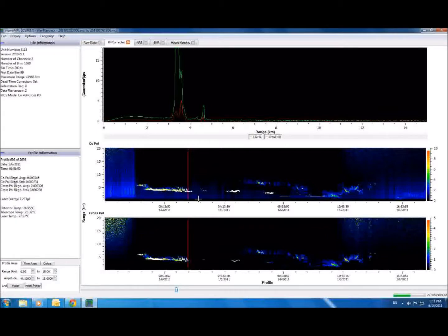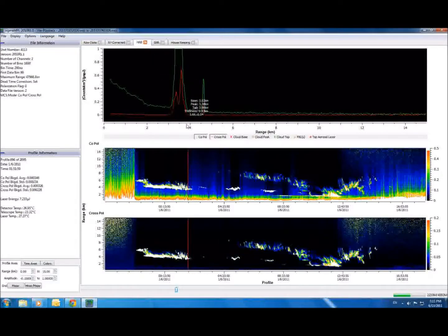The next step in post-processing is what we call the NRB, or Normalized Relative Backscatter tab. In these graphs, we have compensated for several other calibrations, including the after pulse, overlap, and dead time factors inherent in all LIDAR systems. Notice also that this graph adjusts itself to minor fluctuations in laser energy.